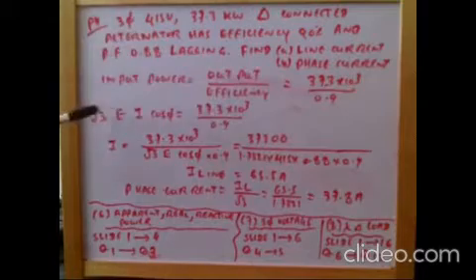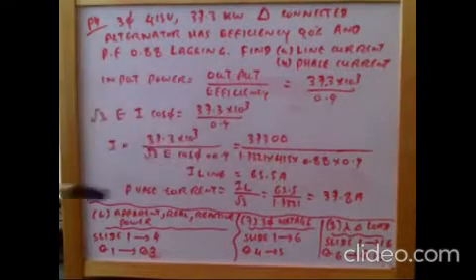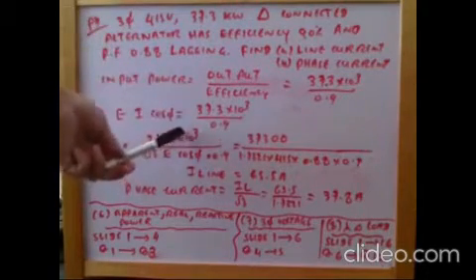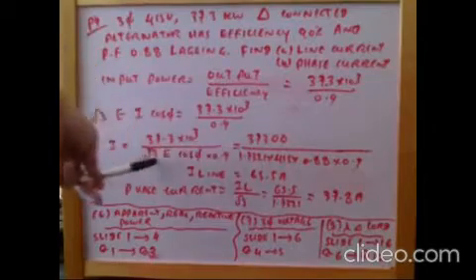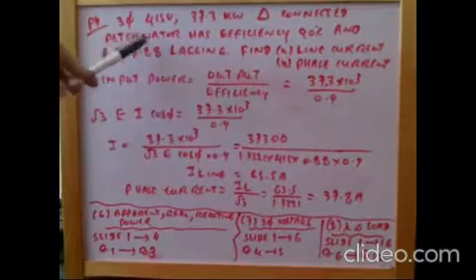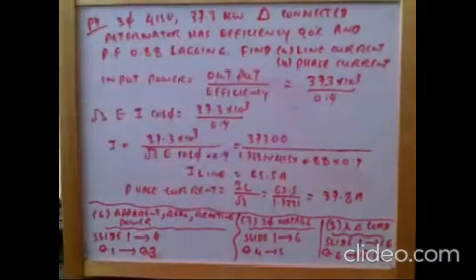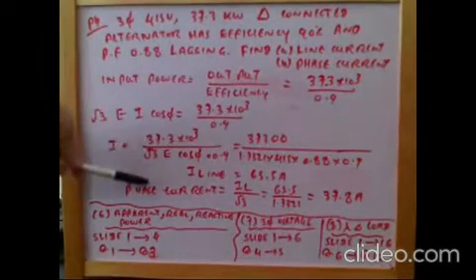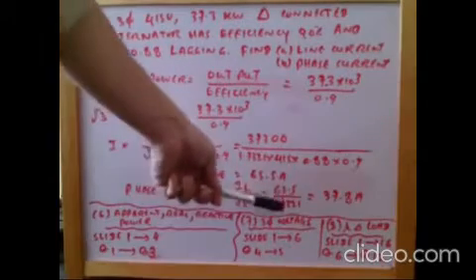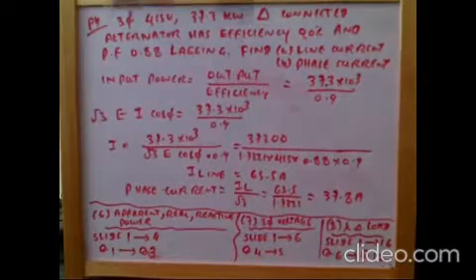Input power equals root 3 times E times I times cos φ. Rearranging for I: power divided by (root 3 × E × cos φ). Substituting: power is 37.3 × 10³, root 3 is 1.732, E is 415 V, and power factor is 0.88. The line current is 65.5 A. For the delta connection, phase current equals line current divided by root 3: 65.5 / 1.732 = 37.8 A.